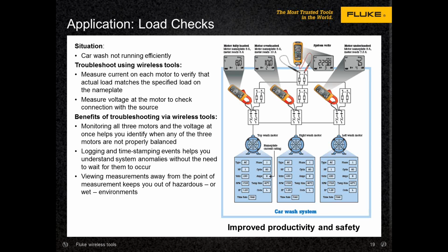Right. Can you tell me a little bit about inrush? Inrush allows you to measure the startup current of a motor, because any time you have a motor that turns on from the off position, there is a huge spike that occurs at startup, and depending upon the type of motor and the design of that motor, that startup current will vary. There are some industry standard inrush numbers associated with certain types of motors depending upon the motor rating. So that's one way to tell motor health in the case of startup.